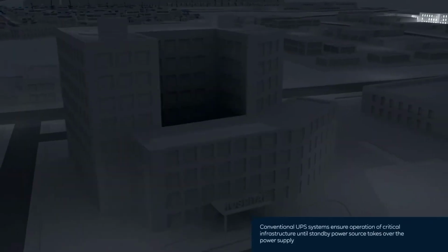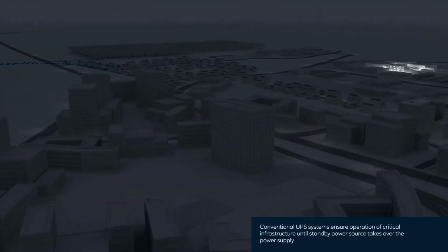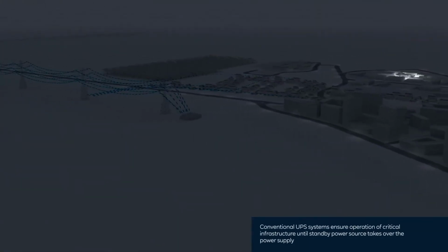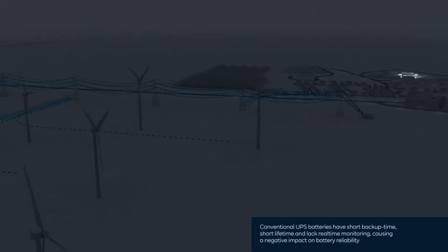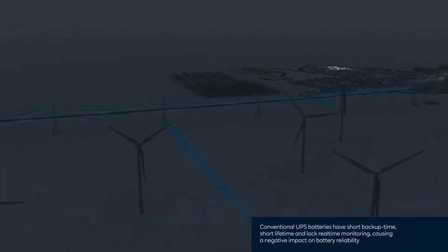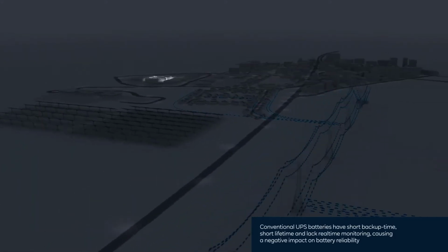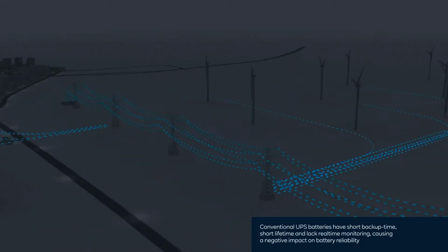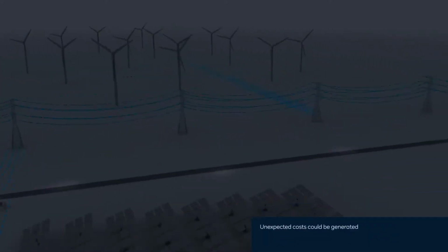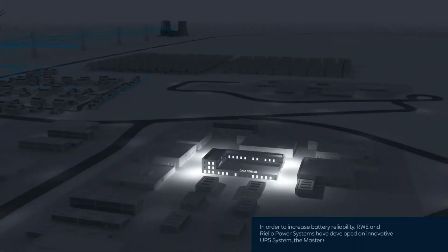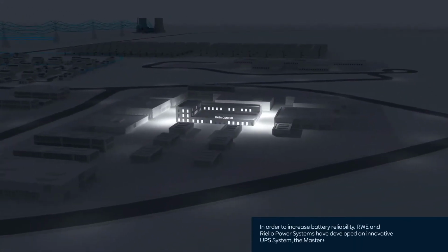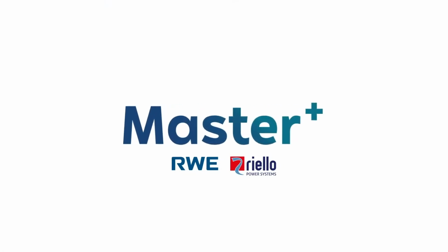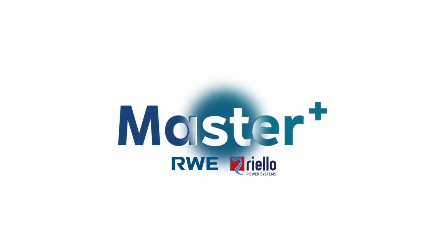Even though conventional UPS systems ensure the operation of the facility until the standby power source takes over the power supply, their batteries have a short backup time and lifetime and lack real-time monitoring. This has a negative impact on battery reliability and could generate unexpected costs. In order to increase battery reliability, RWE and Riello Power Systems have developed an innovative UPS system, the Master Plus.